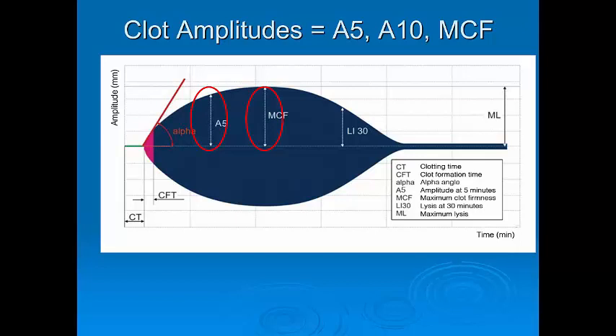The amplitude or clot strength is measured at a number of different time points. MCF stands for maximum clot firmness; however, this usually occurs around 30 to 40 minutes, and in most clinical situations you want to be able to make a decision before waiting this long. Most algorithms now use A5 or A10 — the amplitude at 5 or 10 minutes.